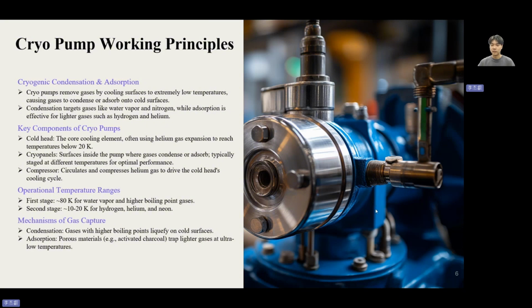Usually the pump has two main temperature stages. The first stage is around 80 K, and it mainly traps water vapor and other gases with relatively high boiling points.